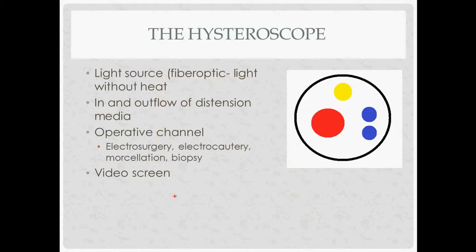How the hysteroscope itself works: you have a light source and a camera using fiber optic light, which gives a nice light without heat and allows you to see what's going on. You have inflow and outflow of the distension media. Then you have the operative channel, where you put in whatever tools you need — electrosurgical tools, electrocautery tools, things to morcellate or biopsy. You see what you're doing on a video screen.